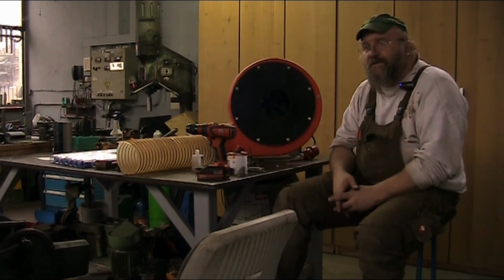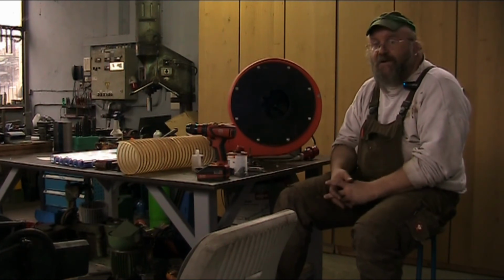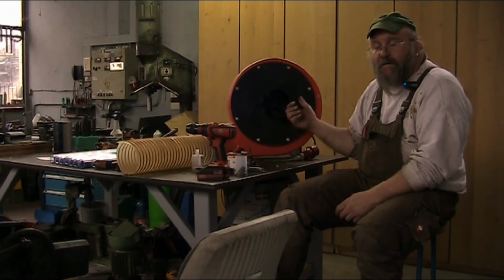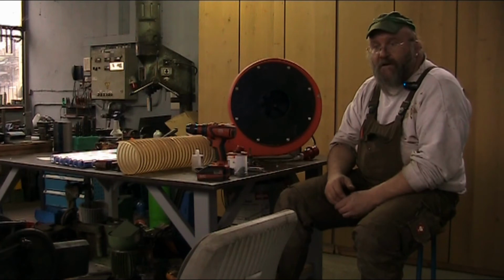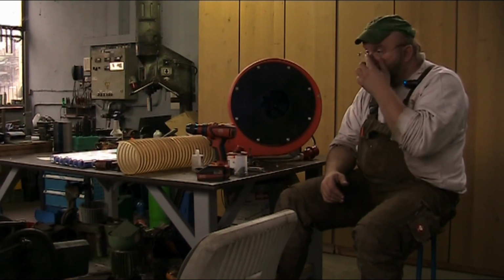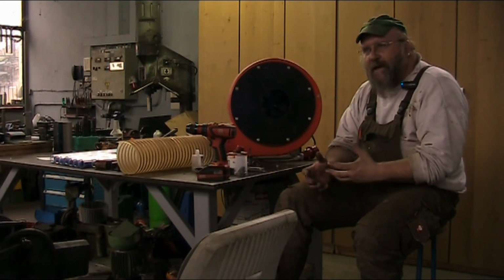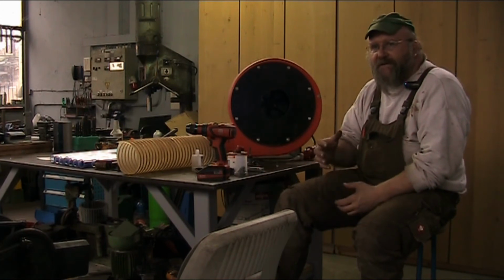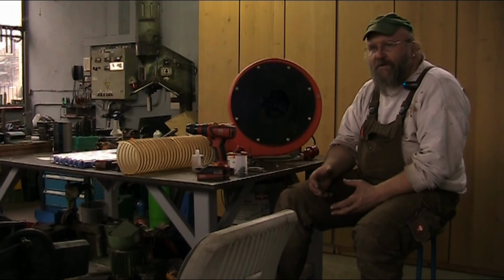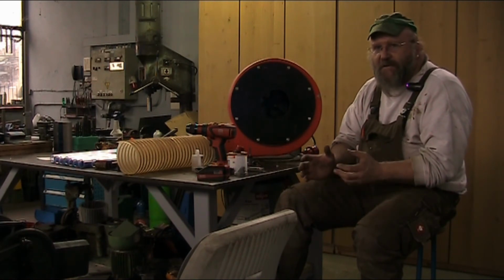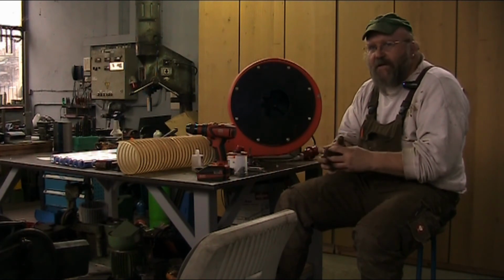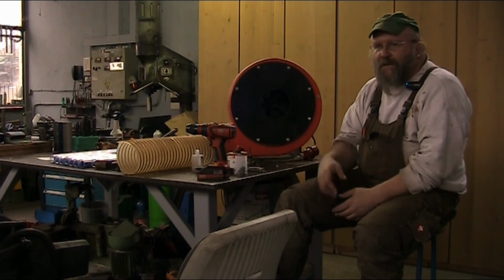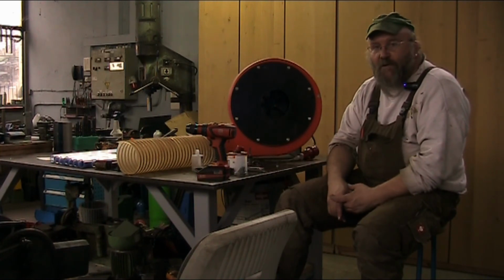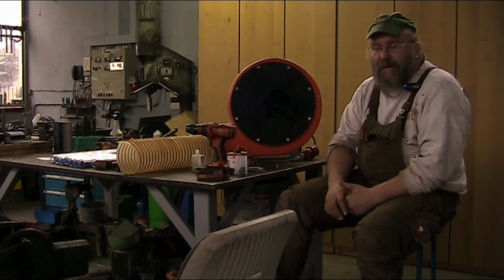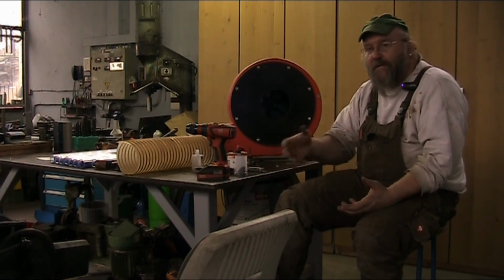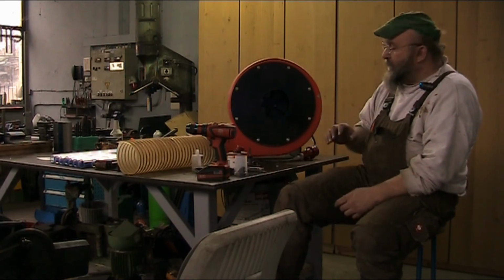You'll have some cavitation issues, which in turn manifest themselves in increased noise. And then also the RPMs on the blower will increase. It's not because you're creating a heavier load, it's because you're actually creating less of a load. The impeller is designed to turn at a certain RPM and run under a certain load. You'll experience this with your vacuum cleaner when you hit something solid and it plugs the tube and then the motor revs up. That's because the impeller is running essentially in a vacuum, and it allows the motor to turn at a higher RPM. As soon as you take it off, there's a load back on the motor, and the RPMs drop back down to where they need to be, and that's the reason for that.